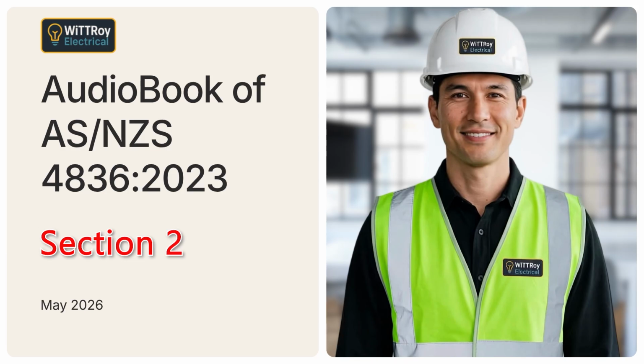Section 2. Principles of Risk Management. Today we're moving into Section 2 of ASNZS 4836. This section is about risk management. The main idea is simple. Before work starts on or near any electrical installation or electrical equipment, a competent person must decide whether the work can be done safely. Electrical safety is not based on guessing. It is based on identifying hazards, assessing the risks, choosing suitable controls, and checking that those controls are still working. If the risk cannot be controlled enough for the work to be done safely, then the work must not go ahead.